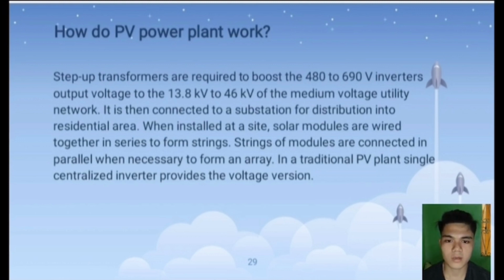Step-up transformers are required to boost the 480 to 690 voltage inverter's output voltage to the 13.8 to 46 kV of the medium voltage utility network. It is then connected to a substation for distribution into residential areas.